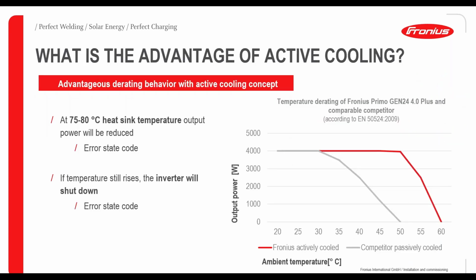In the next slide, we can shortly see what difference it makes if we talk about active or passive cooling. In this graphic on the right side, we can see the output power according to the ambient temperature. And we have a comparison here. The red line is a Fronius Primo GEN24 inverter, actively cooled, and the gray line is a competitor which is passively cooled. And we can see there, of course, the passively cooled system is derating much faster and at a lower temperature range than the Fronius inverter. Here we talk about 50 degrees where the Fronius inverter starts to derate.